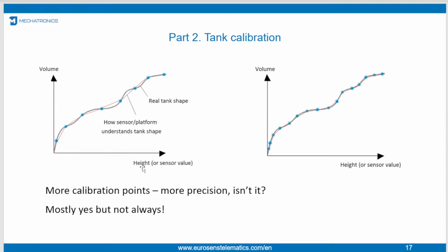If we put tank calibration data on a plot, we will get a chart like this one. How does the sensor or your software platform calculate volume when the level is between our calibration points? Let's imagine that our points are connected by red straight lines between points. When a new level measurement comes, the sensor looks up this chart, finds the point on this imaginary red line, and receives the volume. And here is a very important outcome from it.